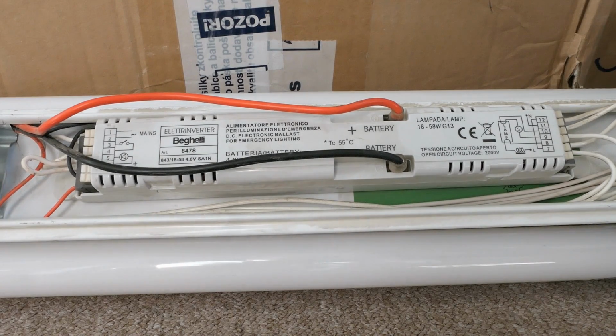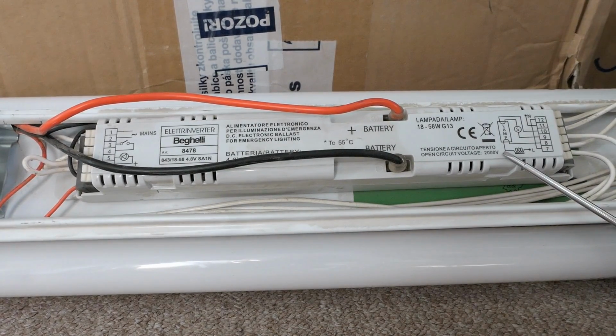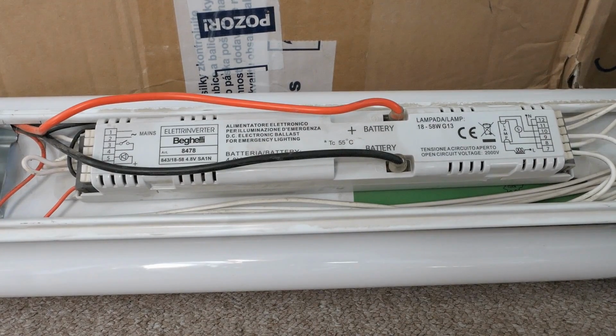And this one only backs up one of the tubes in the fixture, and it definitely doesn't run it at its full power, I guess just a fraction of it. It doesn't have access to this pin of the lamp, so it's probably running it in cold cathode mode, which quickly destroys the emissive layer, but in backup mode it probably runs only a few hours a year, so you can get away with it.